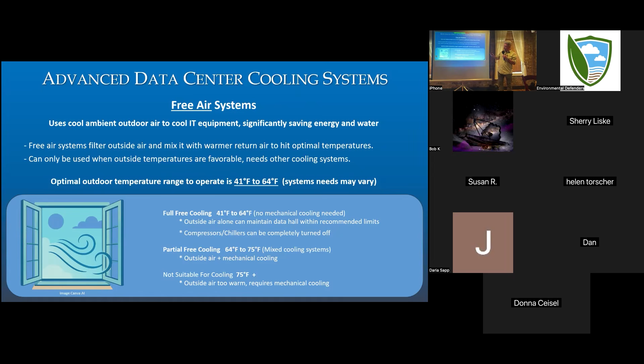So that optimal line from 41 to 64 degrees can be full free air, where they don't need any other additional cooling. Once it gets a bit warmer, from 64 to about 75, you may need both the free air and cooling system, and above that, you need full air conditioning. These are relative numbers - different systems will have different numbers, but I've spoken to people in the field, and this is a fairly consistent number I came up with.